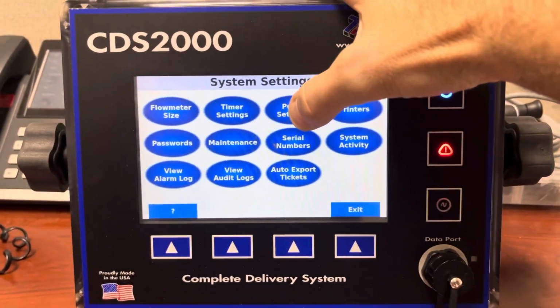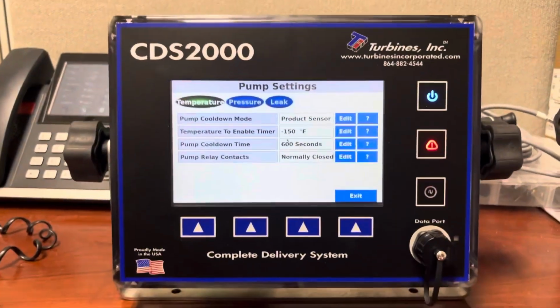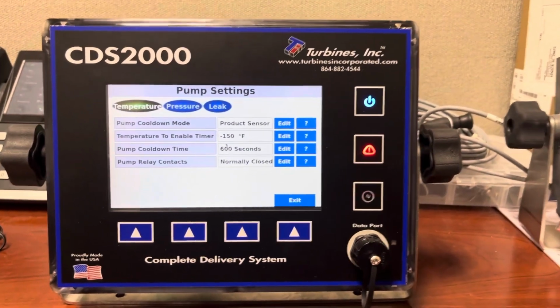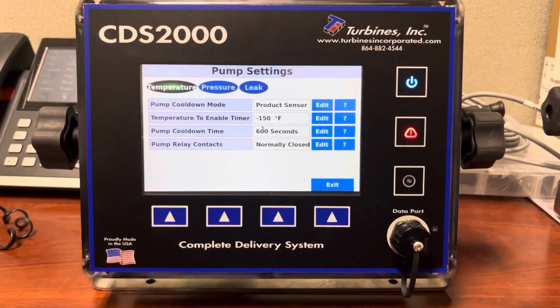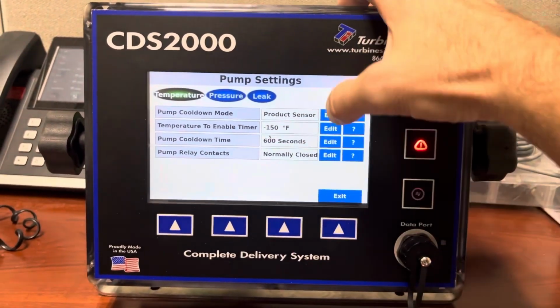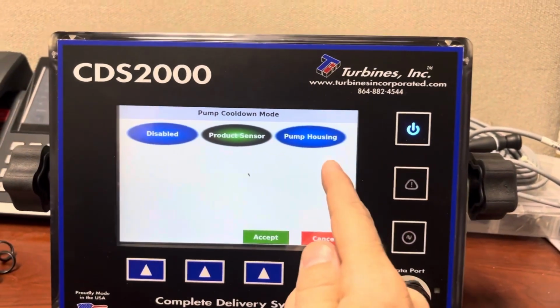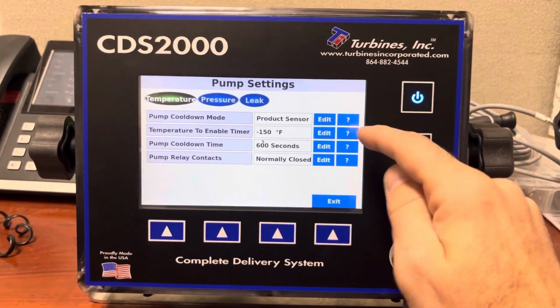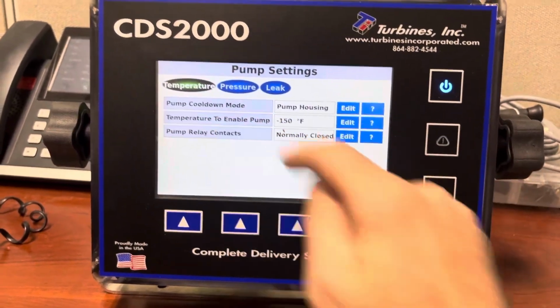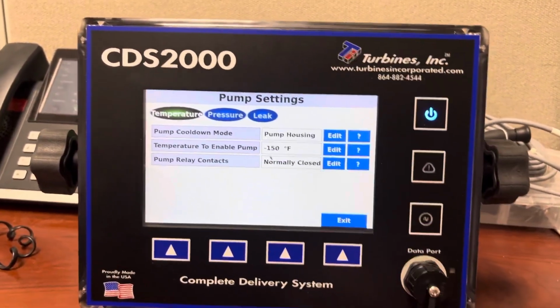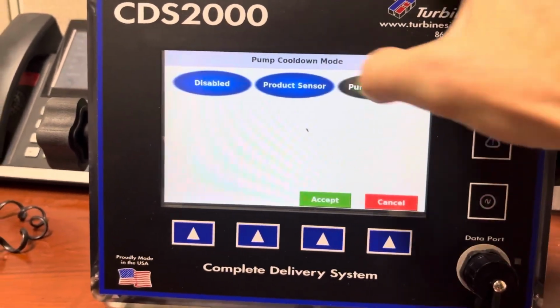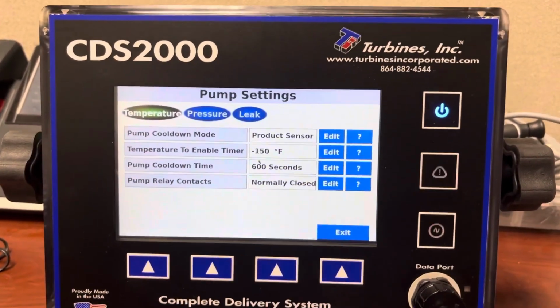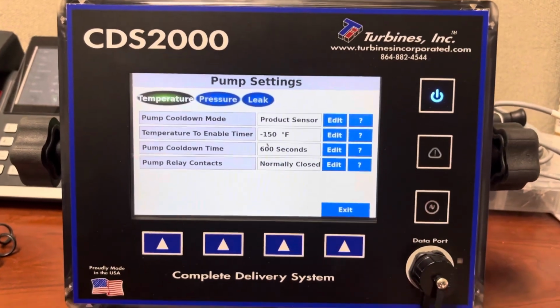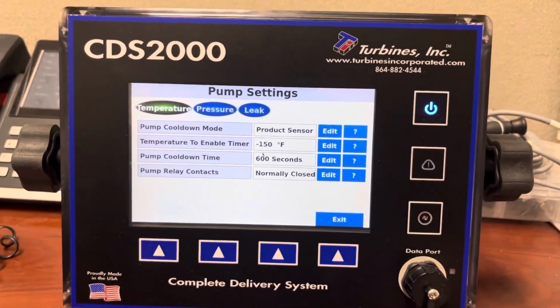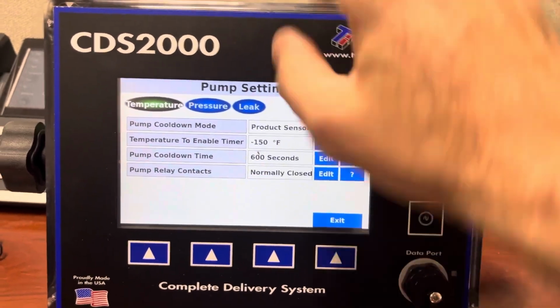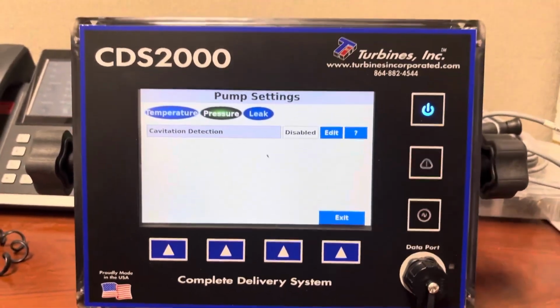But then finally, really the last one that you're going to have to get involved with is pump settings. This is where you set up either your cool down through your RTD or your cool down through your pump housing sensor. And that's all done here. Cool down mode, you can either disable it, you can use the product sensor or the pump housing sensor. If you turn your pump housing sensor on, you'll see that the timer feature is removed from this submenu. But if you use your product sensor, the timer populates back. So it's temperature and timer when you use product sensor, but it's only temperature when you use the pump housing sensor. There's where you can find your relay contacts, and then you have your pressure sensing here.